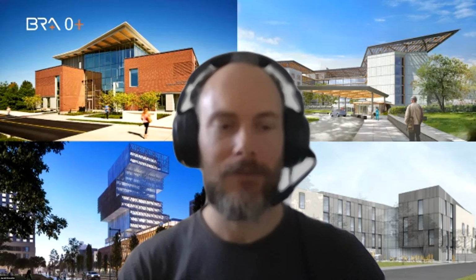You really want that interior maintenance so there's nothing outside, or do you want to go with a less expensive option and put in air source heat pumps rather than having components outside that need maintenance outdoors? That's a process the team would need to evaluate, but you can definitely drive the demand down for a 50,000 square foot building to a very low point with the technology available today. Given how the technology on air source heat pumps is moving, do you anticipate a point where people wouldn't do geothermal anymore because air source heat pumps are so efficient? I think at some point in the future, for new buildings, people will not be considering geothermal because the air source technology is advancing so quickly.